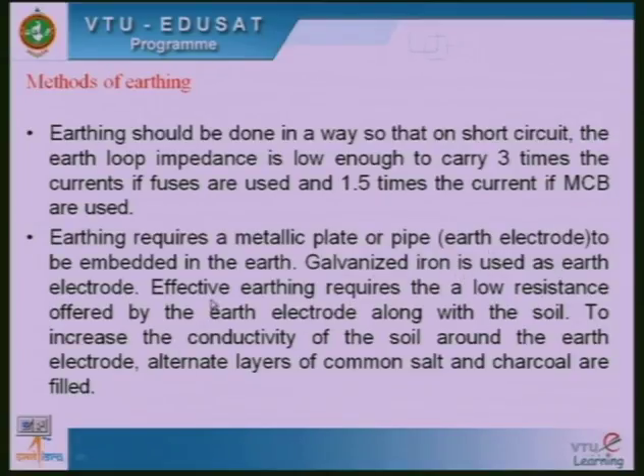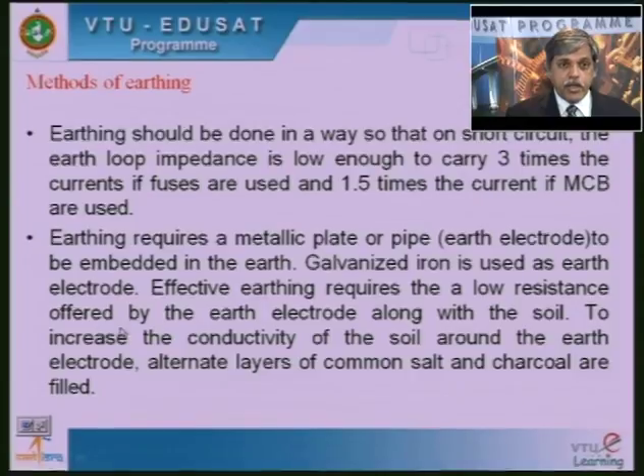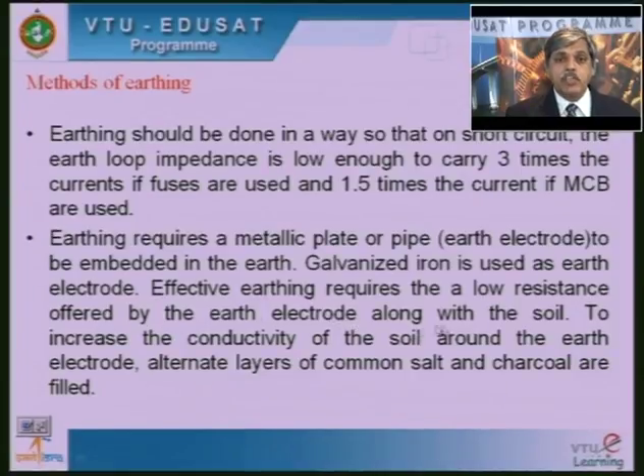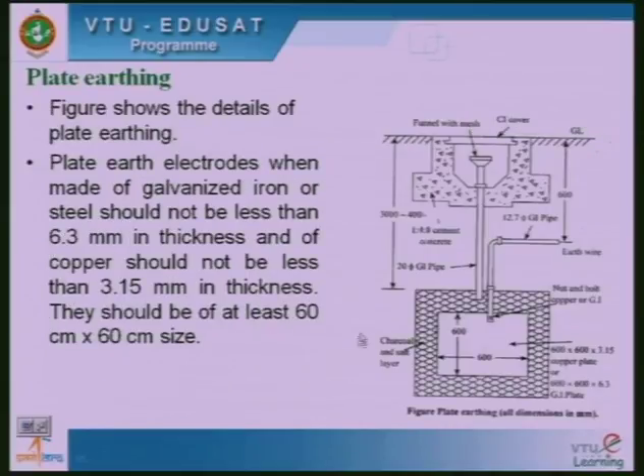Effective earthing requires the low resistance offered by the earth electrode along with the soil. So to increase the conductivity of the soil around the earth electrode, we provide alternate layers of common salt and charcoal. So, we have plate earthing. Suppose I am using a galvanized iron plate as an earth electrode, then I will call it plate earthing. This is the physical dimensions of the earth plate earthing.